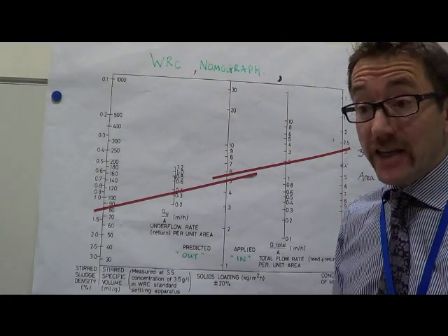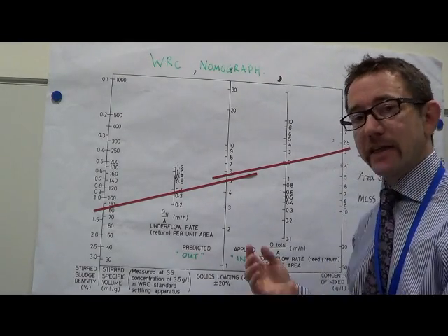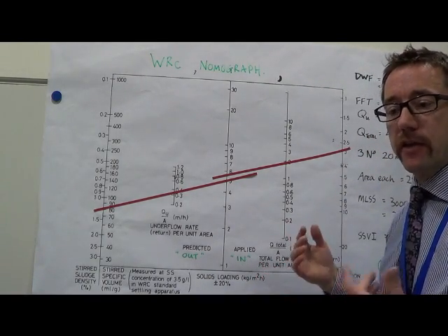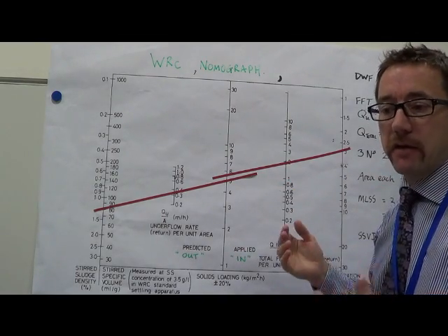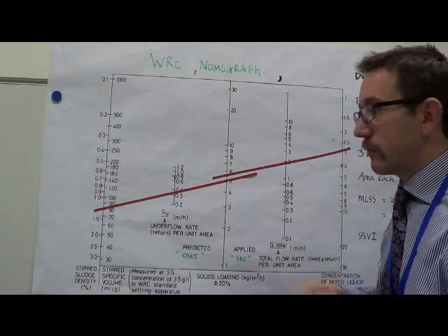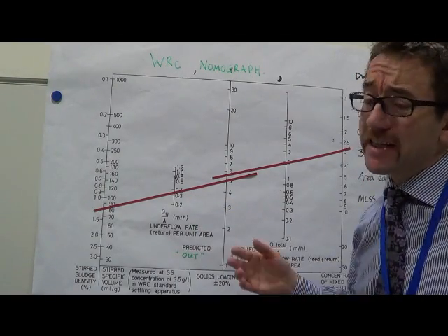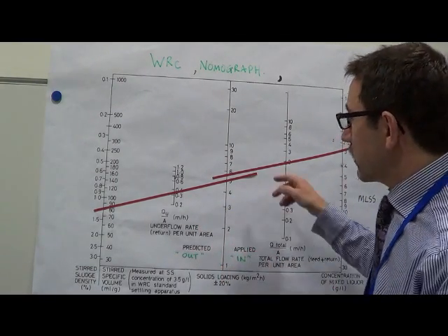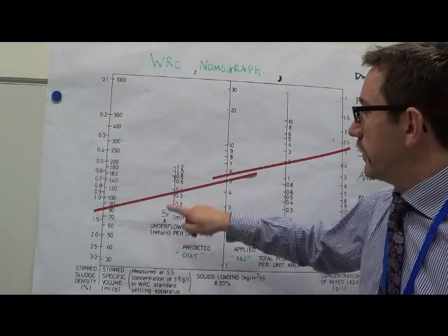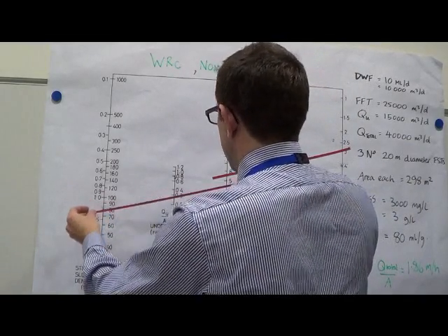I was at Redditch just yesterday actually, and they had exactly this problem. They were struggling. They had quite a high sludge blanket in their tanks, and it was because they had some sort of blockage on their RAS line, and it was reducing that flow. In fairness, in Redditch it was completely blocked. So again, you can see that it's very sensitive to having anything go wrong with your RAS flow rate. So that's a really important parameter, and again, it's why it's a golden measure.